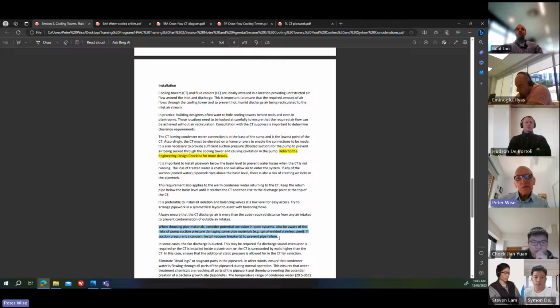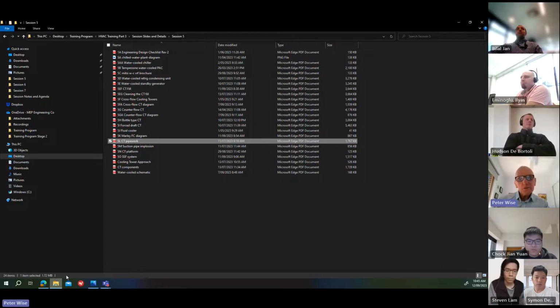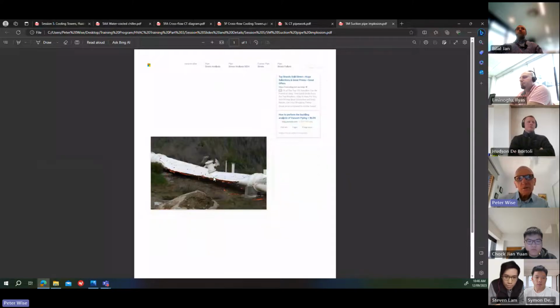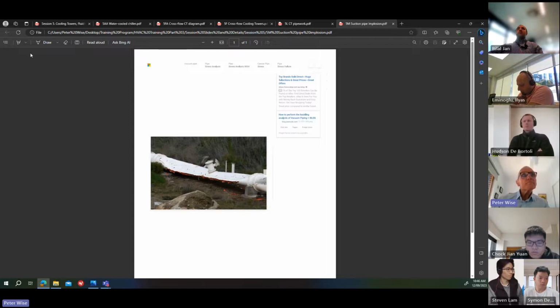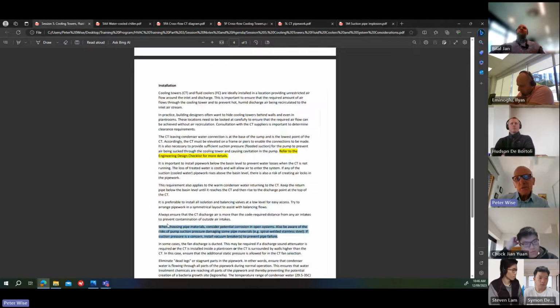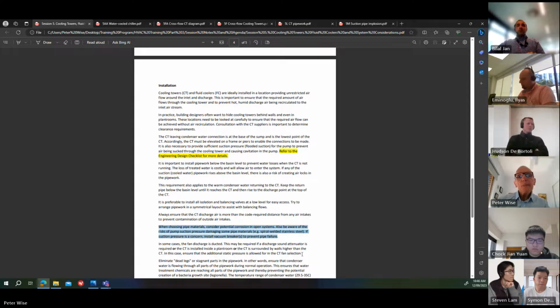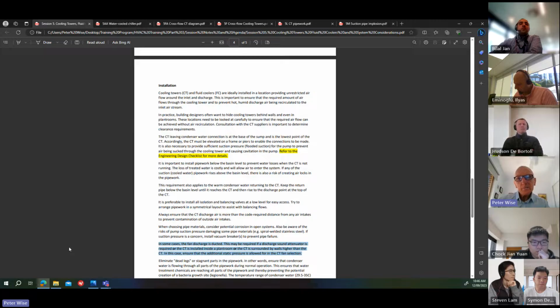If they close the suction valves on the cooling tower and the pump is still running, you're going to create a high suction pressure in that pipe. And I'll show you a picture of, this is actually not a condenser water system, but this is what will happen. If you're using spirally welded stainless steel for condenser water, and someone does that, leaves the pump running and shuts the valves, it'll just go boom and collapse. And I've seen it several times, to be honest. And so that also comes down to selection of materials. So if you want to use spiral welded stainless steel to save money, be very careful that doesn't happen. Something to be aware of. You can get seamless stainless steel, and you won't have any problems with that, but it's obviously a lot more expensive.